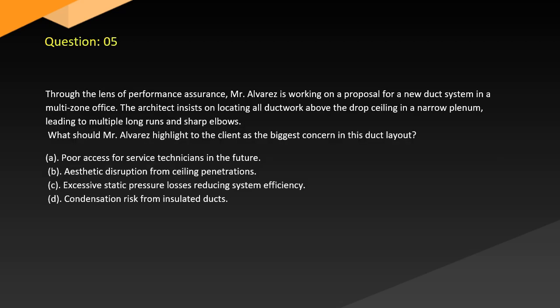Question 5. Through the lens of performance assurance, Mr. Alvarez is working on a proposal for a new duct system in a multi-zone office. The architect insists on locating all ductwork above the drop ceiling in a narrow plenum, leading to multiple long runs and sharp elbows. What should Mr. Alvarez highlight to the client as the biggest concern in this duct layout? A. Poor access for service technicians in the future. B. Aesthetic disruption from ceiling penetrations. C. Excessive static pressure losses reducing system efficiency. D. Condensation risk from insulated ducts.